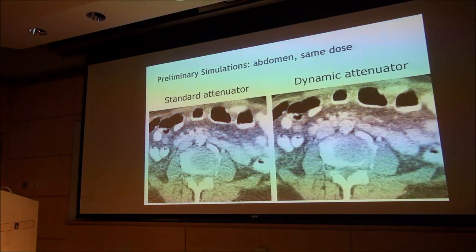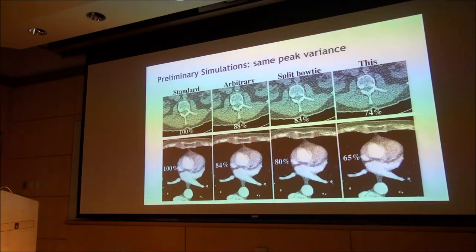Here's a simulation of what the benefits should be. Here's a scan of the lumbar spine at the same dose with a standard bowtie versus a dynamic attenuator. The noise level is lower. If you want to keep the noise level the same and ask how much dose reduction you can get, the percentages you see are the dose for the same peak variance. This is a standard bowtie, this is the piecewise linear dynamic bowtie. 65% the dose, and the noise is more visually appealing because it's less streaky.